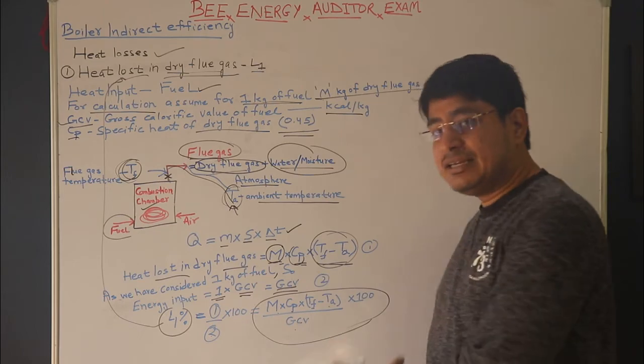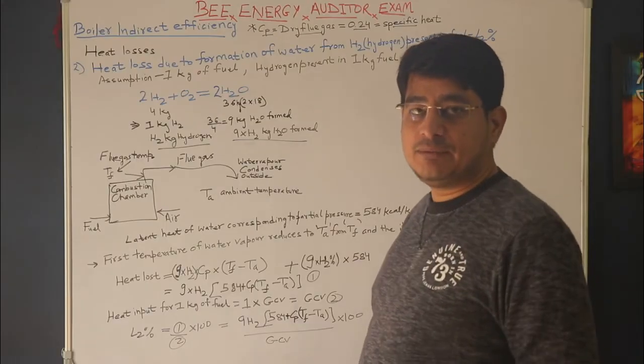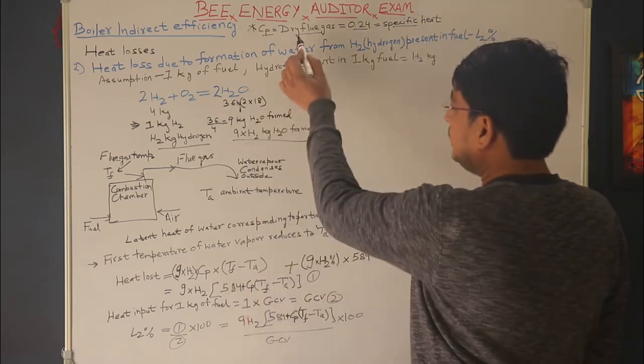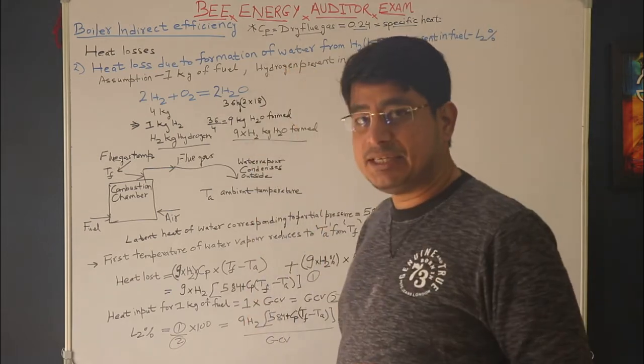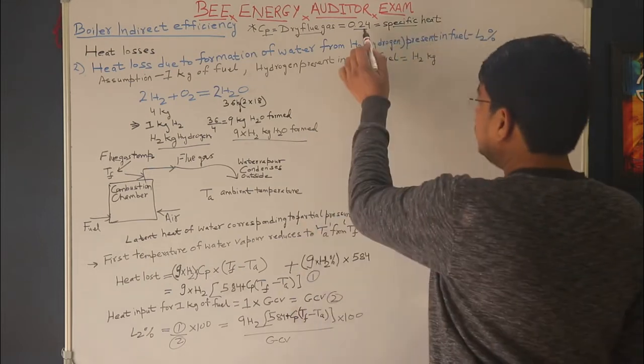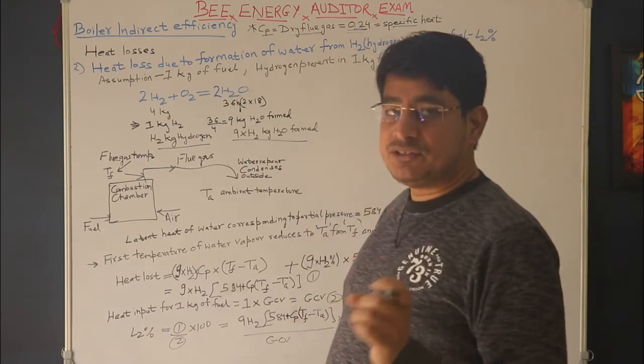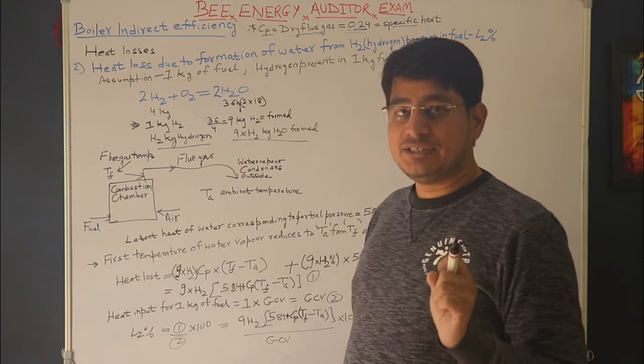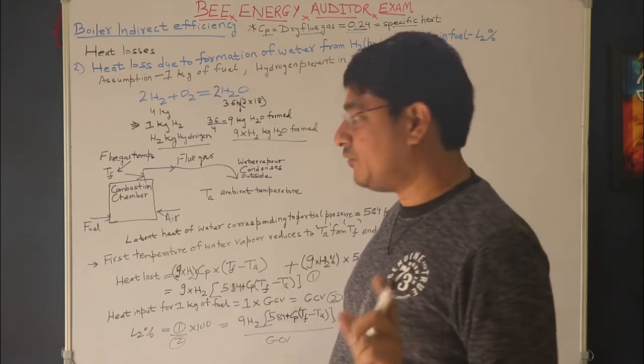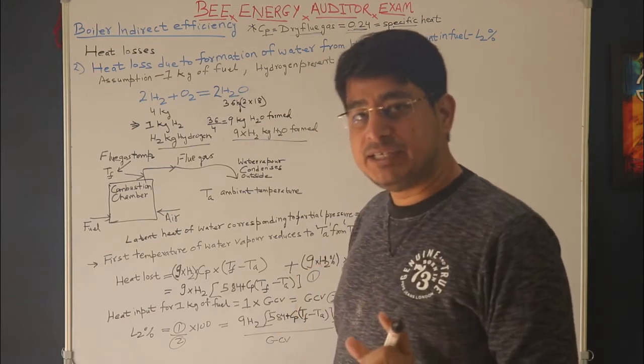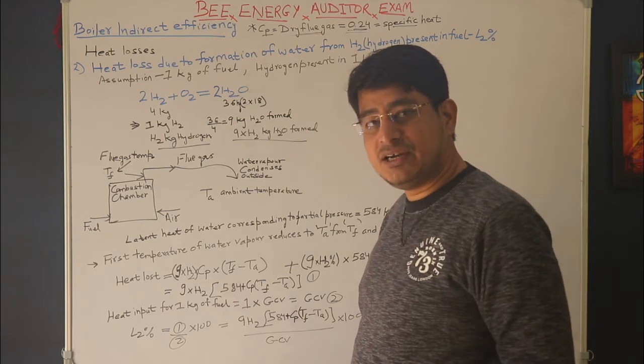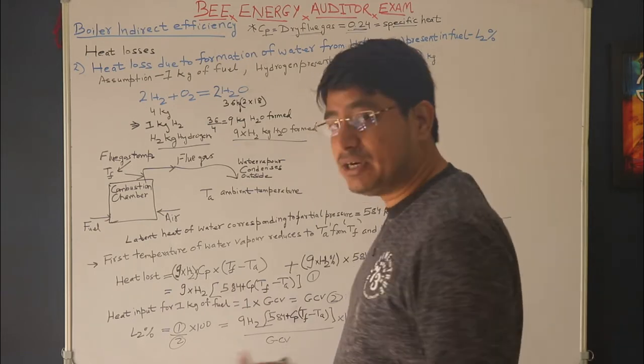Before proceeding, a correction: the specific heat of dry flue gas, Cp, if not given, should be assumed as 0.24 — not 0.45. The value 0.45 is the specific heat of wet flue gas or water vapor.